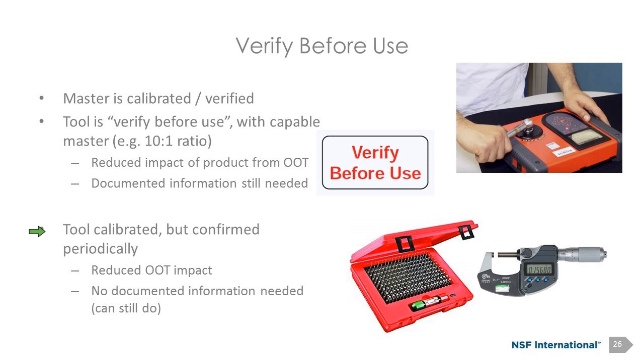I see a lot of companies that do calibration of the tool and then they reconfirm it periodically anyways. So that means my torque wrench is calibrated or verified, my torque meter, my torque analyzer is calibrated or verified, and then I'm still, on a daily basis or per shift basis, whatever it might be, going to plug this into here and make sure that it's reading the correct inch pounds. That's great because that's going to help us reduce the risk even further by limiting the amount of product exposure for one of those out of tolerance events.